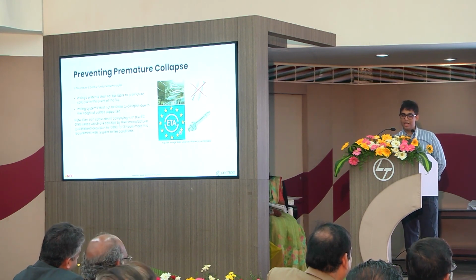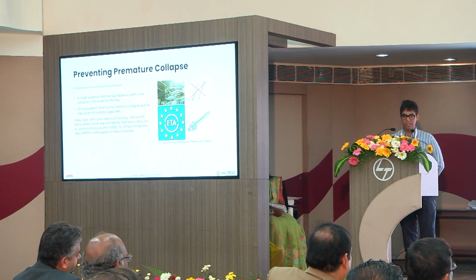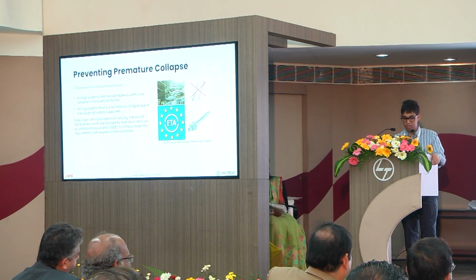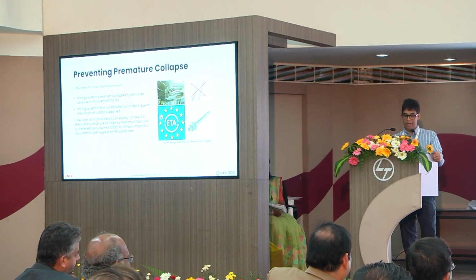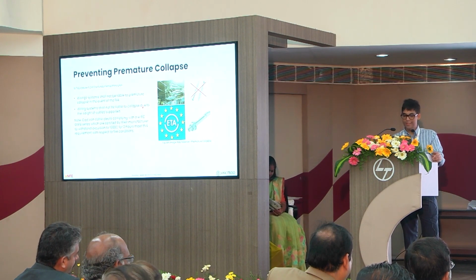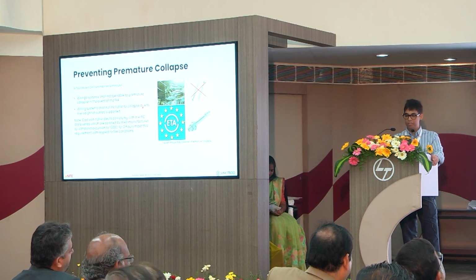But the basic idea is that ETA approved anchors, such as steel anchors, should be used. And cast iron cable cleats, etc., complying with 61914 are a good idea. Usually the manufacturer will say that this can withstand excursion to 1000 degrees Celsius for 2 hours. That way we meet this requirement.